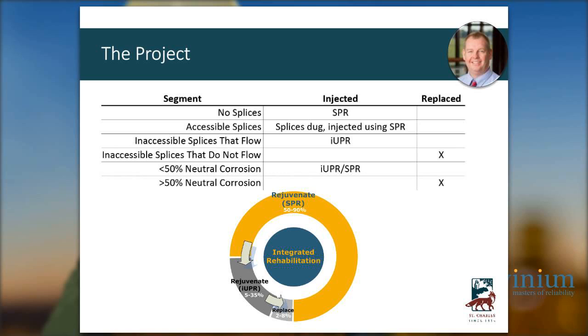If there are accessible splices that would otherwise block the flow of the fluid, we dig those splices up and inject using a special splice that lets you inject from the splice back to the termination point, whether on a pole or in a transformer. Sometimes we'll skip a splice if we didn't know it was there; other times we'll dig it up ahead of time and go right to it, injecting both ways.